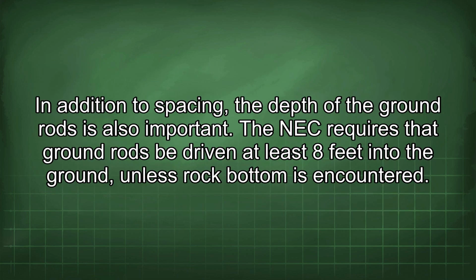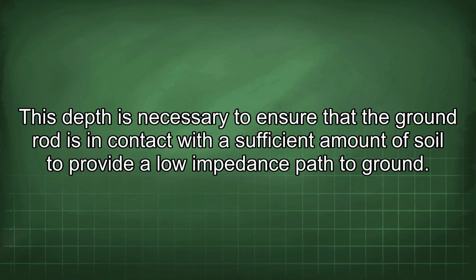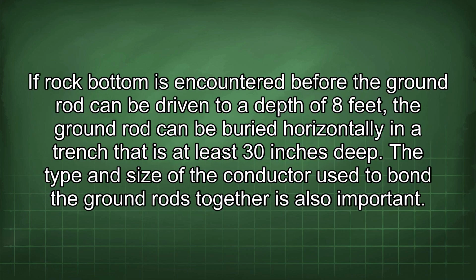In addition to spacing, the depth of the ground rods is also important. The NEC requires that ground rods be driven at least 8 feet into the ground unless rock bottom is encountered. This depth is necessary to ensure that the ground rod is in contact with a sufficient amount of soil to provide a low impedance path to ground. If rock bottom is encountered before the ground rod can be driven to a depth of 8 feet, the ground rod can be buried horizontally in a trench that is at least 30 inches deep.